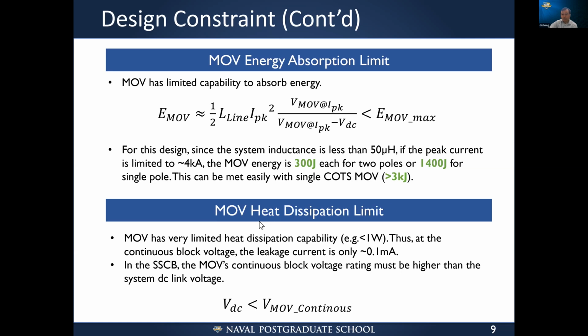Another thing is, after the fault is cleared by the breakers, the MOV in the worst case will need to block the full DC link voltage. These are resistors. When you see a voltage across it, you will see a leakage current flowing through it. So even though the MOV can temporarily absorb a lot of energy, a few kilojoule, it has a very poor or limited heat dissipation capability, typically less than 1 watt. So for continuous blocking voltage, the leakage current must be only in the range of 0.1 milliamp, because you are blocking 2 kilovolts.